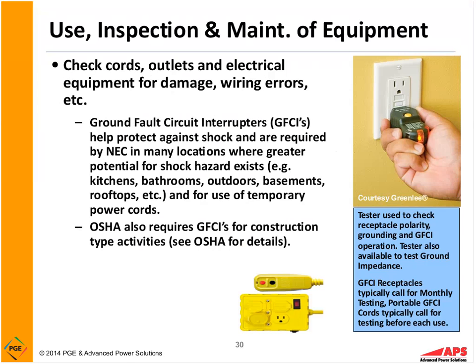Now, that provides protection for low-level shock hazards. So in other words, at very low levels of current, it trips, should we have someone that gets between an energized conductor and the ground, whether that be the ground you're standing on or a ground wire. But I can also tell you that there are limitations to GFCIs. They do not protect personnel against getting shocked, let's say, line to neutral or phase to phase. It's very important, though, that we check our receptacles and make sure our GFCIs are working properly.